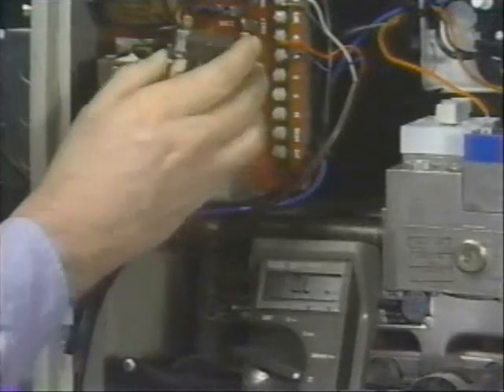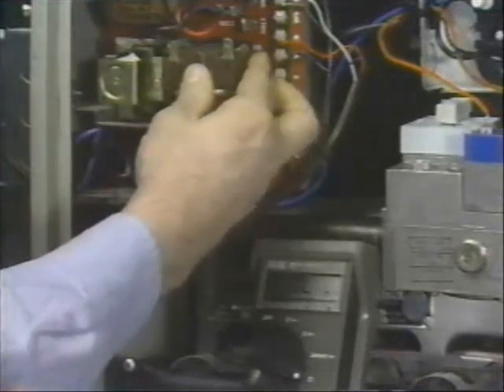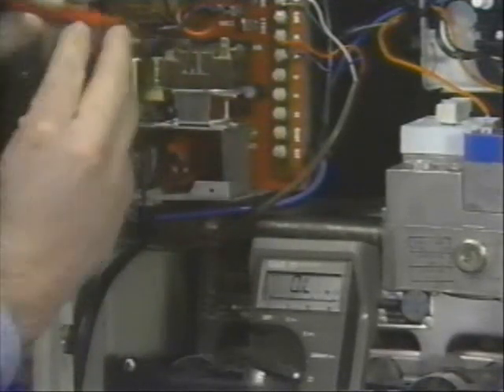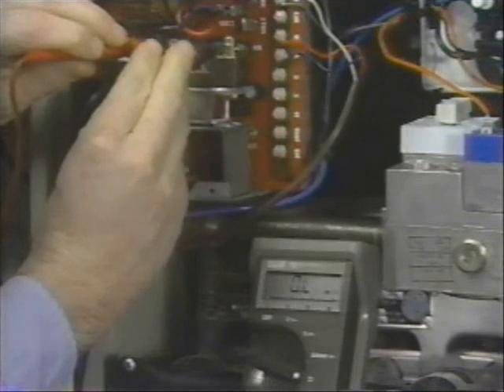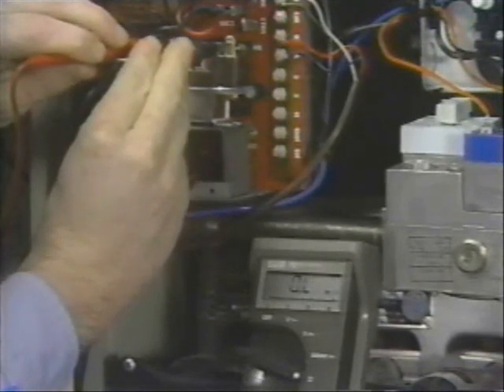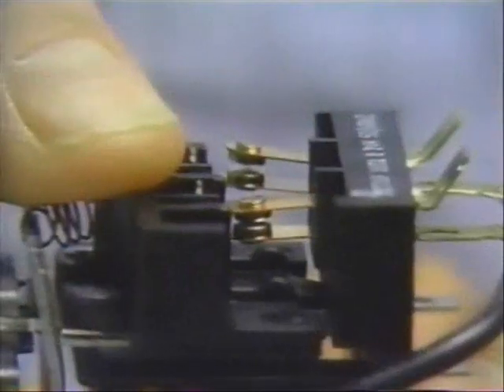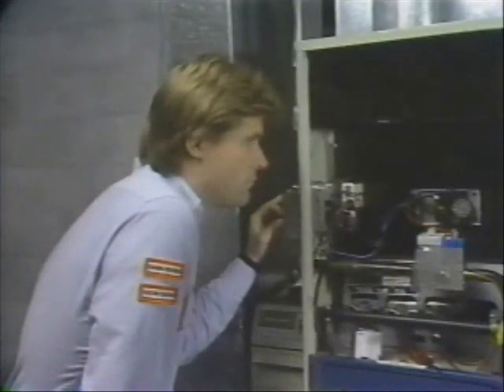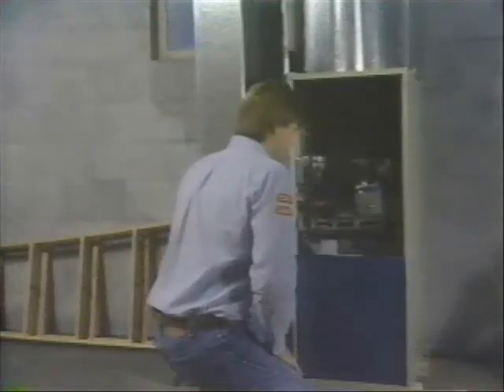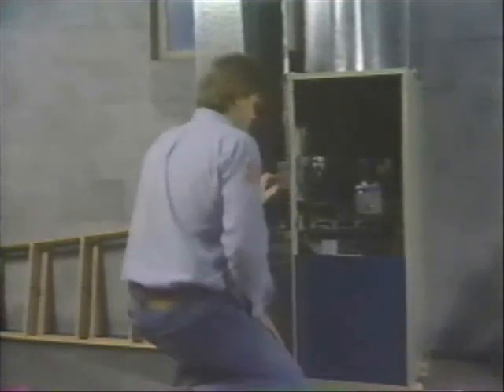You can also check the continuity of the contacts by disconnecting the relay from the circuit and measuring resistance across the contacts. You'll get zero resistance if they're closed, infinite resistance if they're open. On relays with exposed contacts, you should also check to see that the contacts are clean. You can also test the operation of a fan relay by applying power to the coil and listening for the click of the contacts. If the relay is okay, but the fan doesn't operate at high speed, you need to check the wiring and the motor itself.